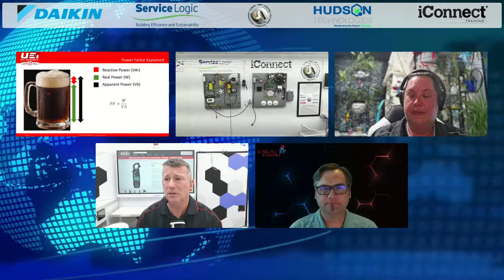Even in our communicating systems, we have a lot of potential for stray voltages on communicating wires, and we're talking about low voltages. If I have a cable, like our internet lines running on a 5-volt DC supply, running parallel to a high voltage wire in an unshielded cable, yeah, 100% we have the opportunity to induce some of those voltages. I've had those scenarios before, even in residential communicating systems, where control wire ran in the same metallic chase as high voltage wire, and we'd get stray voltages causing improper communications. So yeah, absolutely it can happen. That's why it's important for us to have this conversation today.